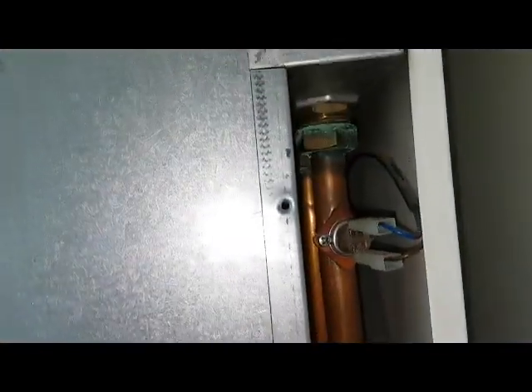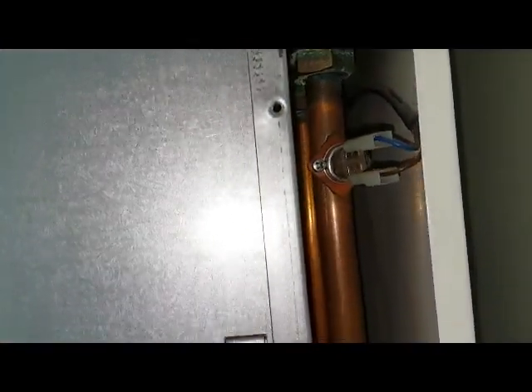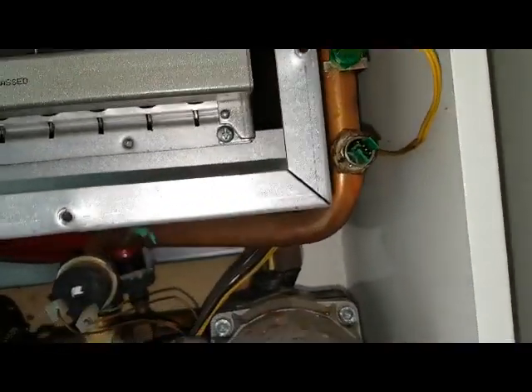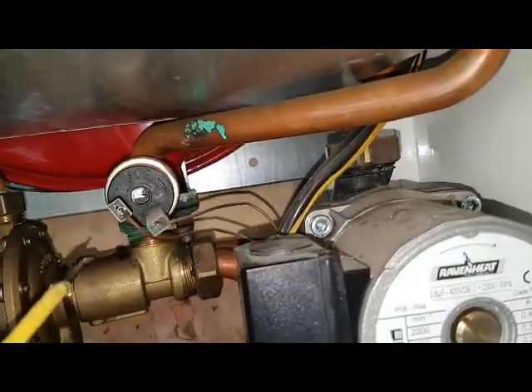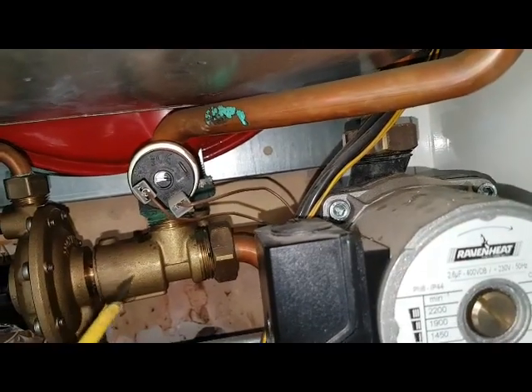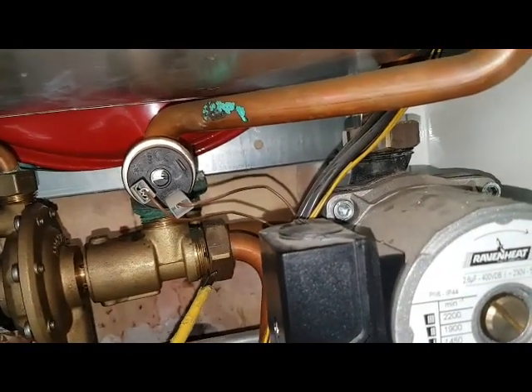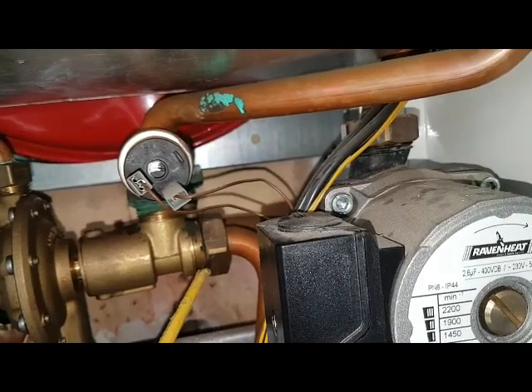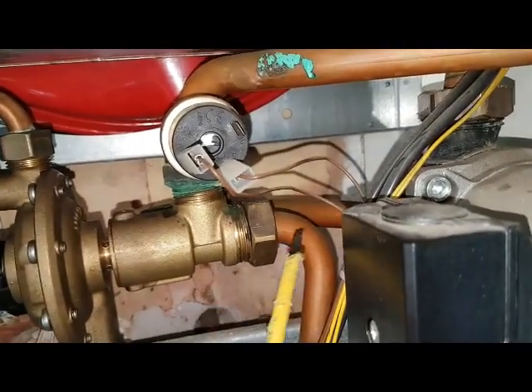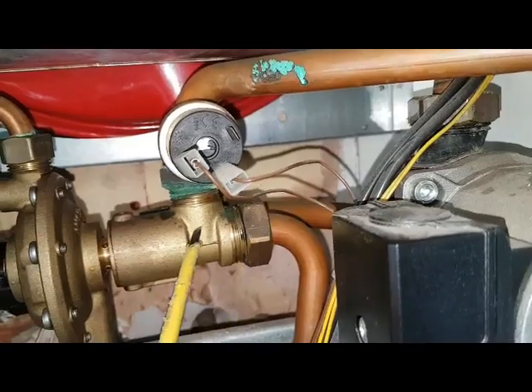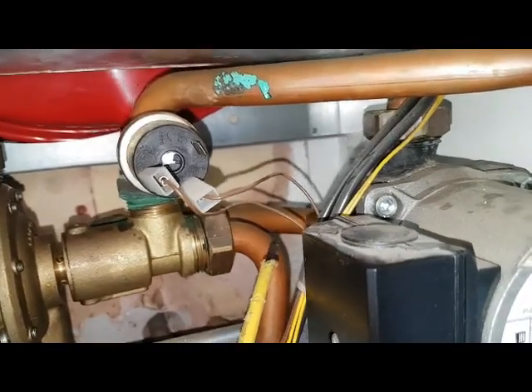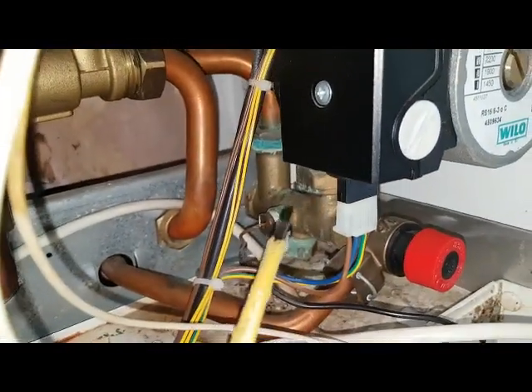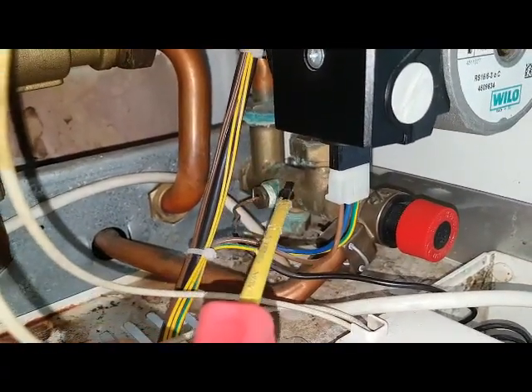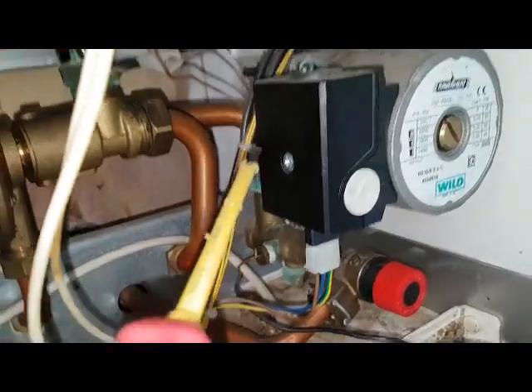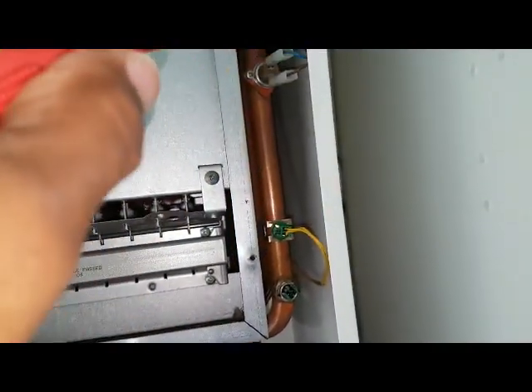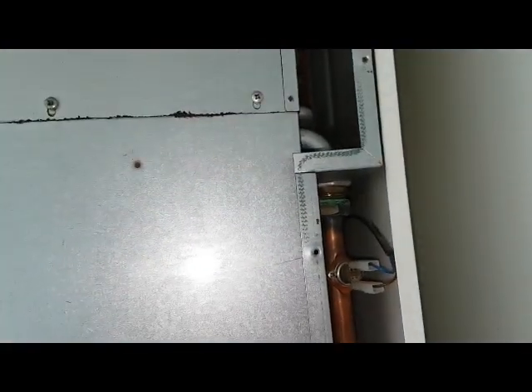So this is the flow pipe, so it's going to come down here as before to the diverter valve. Now this time this port will be shut off so it can't go to the radiators. That pipe at the back is from the back of the diverter. It'll go across down here and back through the pump, up the return into the main heat exchanger.